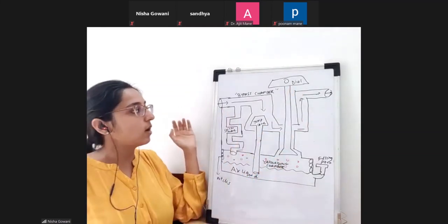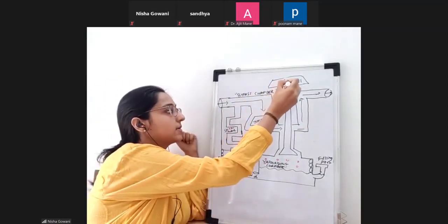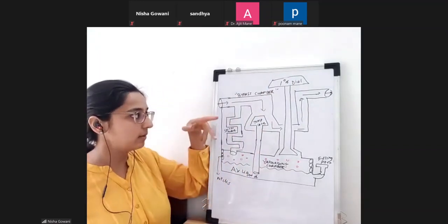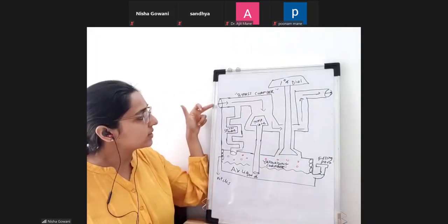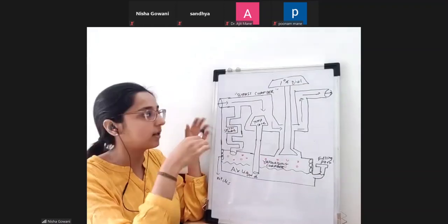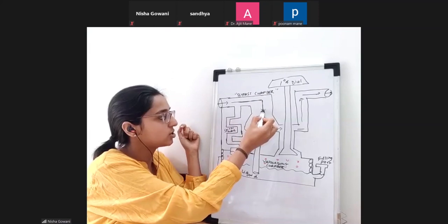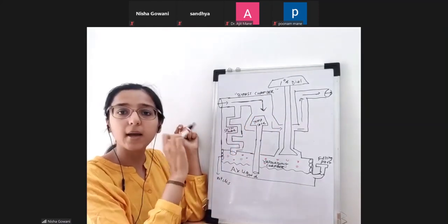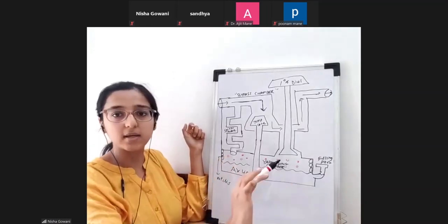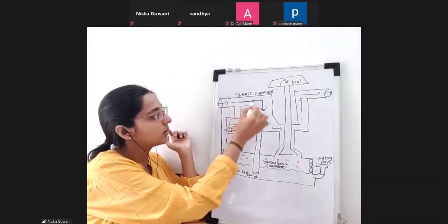Now let's understand, if I switch this on and make this 1%, suppose. I have switched on my dial. Now what has happened? The fresh gas which is going to come, I'm showing with black color. Some amount of the fresh gas will go in the bypass chamber. Bypass chamber means it has bypassed the vapors. Some amount of the gas will bypass the vapors, and they will go like this.